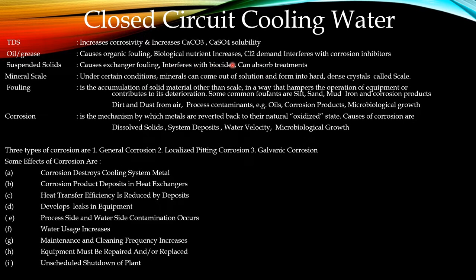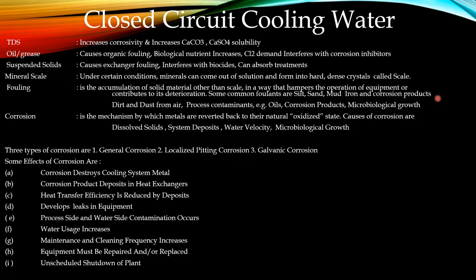Non-oxidizing biocides are affected by suspended solids. Under certain conditions, minerals can form out of solution and form a hard dense crystal called scale — for example, if CaCO3 or calcium sulfate is present, that will form hard scale. Fouling is the accumulation of solid material other than scale that hampers the operation of equipment or contributes to its deterioration. Some common fouling agents are silt, sand, mud, iron, and corrosion products.